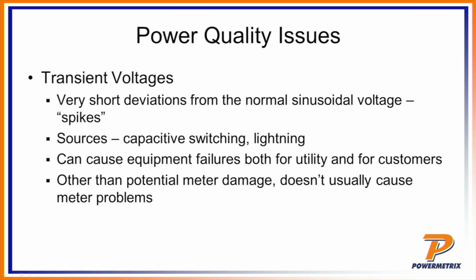Most meters, I shouldn't say most, all meters are really designed to stand up to lightning events. There's a huge amount of energy that goes into that. I can say that since Powermetrix has designed Category 4 safety equipment, we actually design our equipment to withstand lightning strikes, and the simulation of that is a 12,000 volt pulse for a microsecond. A microsecond is 1/1,000,000th of a second, so it's a very short event, but you've got obviously a lot of energy packed into that. Meters, once again, are designed to withstand that. It's got protection equipment that's designed to accommodate that lightning strike coming in and then shunting that energy.